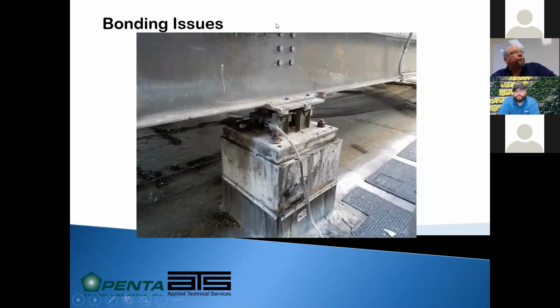This is a cooling tower. They did a bonding connection, but they actually did it below the spring isolation. So this is an isolation connection that prevents vibration of the cooling tower from transferring into the building. But by its very nature, it's isolated, so it's not electrically continuous. So we want to make sure that these connections are up on the body of the cooling tower supports. Our preferred method is actual conductor coming from the top of the cooling tower, if there's air terminals on top of it, to connect those.